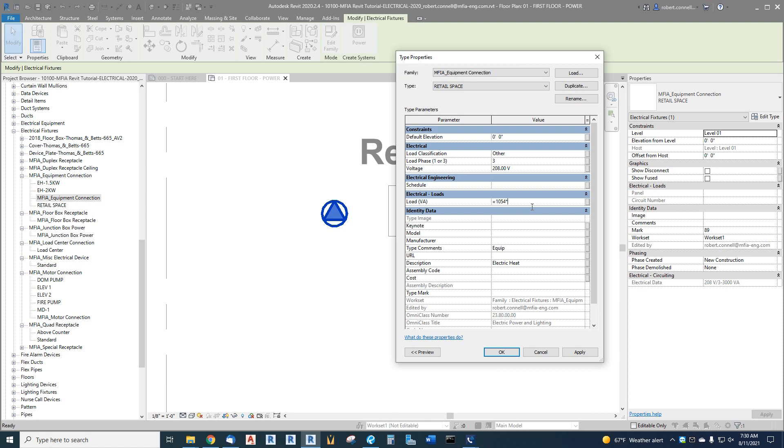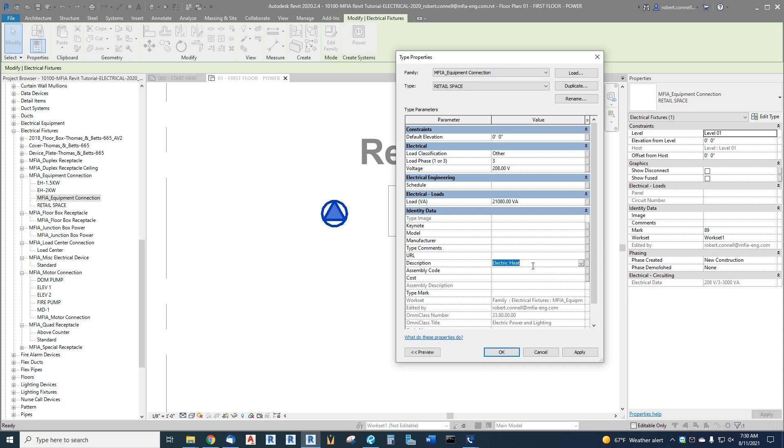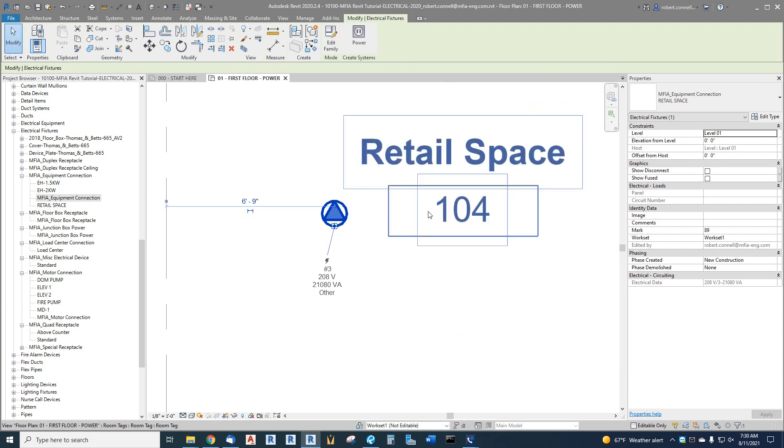In the load you can actually use formulas. You can type in equals 1054 times, kind of like a spreadsheet like Excel, times let's go with 20 watts a square foot. There's our estimated load for that retail at 20 watts per square foot. We do not want this to show up on an equipment schedule, so delete that tag. We will call this—it doesn't matter what we call it. The type mark we will call future retail.